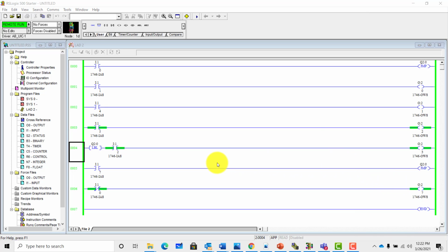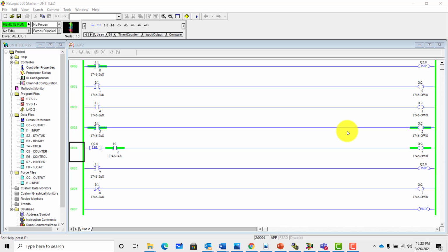Right now, I want to show you how that's going to function. If we press our input 0, we're going to jump down here to this label. Now, we have an output on right now in this program. As I press input 0, you'll notice the output stays on, so it's not like an MCR where you automatically lose your output, but it's no longer scanning this program, so the input state of input 1.5 is no longer controlling the output of output 2.2.